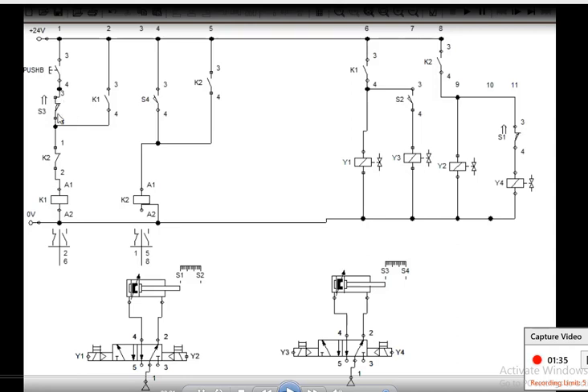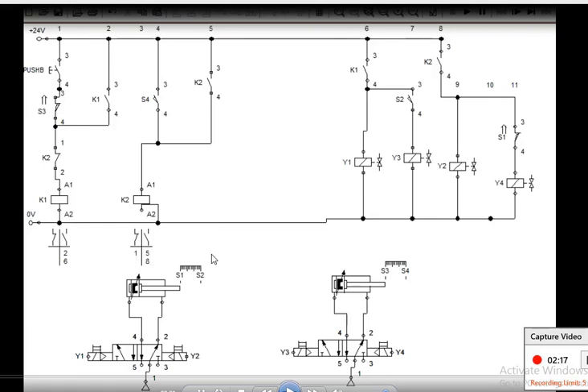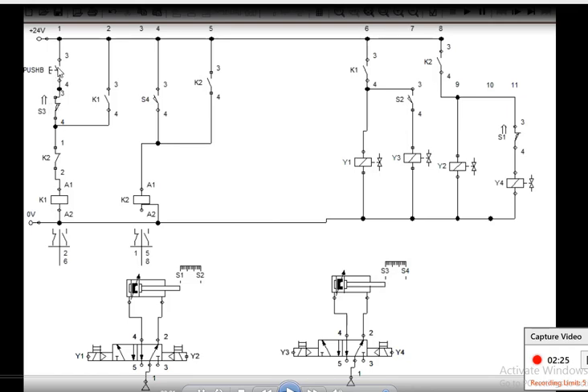The push button has in series an S3 limit switch, which is for the B cylinder. All limit switches S1, S2, S3, S4 are normally open, but S3 is shown as closed here because the cylinder is pushing it — the end of the cylinder actuates it. Similarly, S1 is closed because the piston is at S1. The first limit switch in series with the push button corresponds to the last operation, which is B minus; after B minus the cylinder comes to S3, so I put S3 in series with the push button.